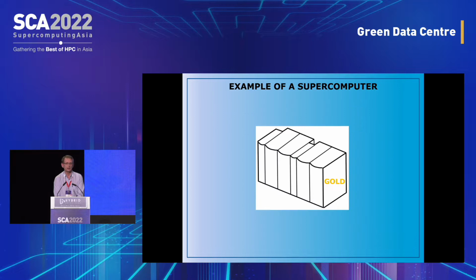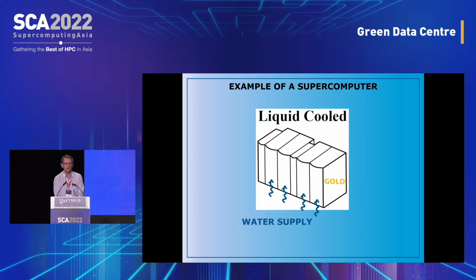Let's go to a practical example. One fine day a client came to me about installing a supercomputer - the gold version, which should be the most fantastic one, right? And it's liquid cooled, good. Look at the front cover of the manual: liquid cooled, very good. Sure enough, we've got a water supply going into the IT equipment cabinets at 16 degrees. Hold on a moment - 16 degrees? This is a liquid-cooled server, right? Oh yes, liquid-cooled supercomputer, gold version. Water return temperature at 20 degrees.